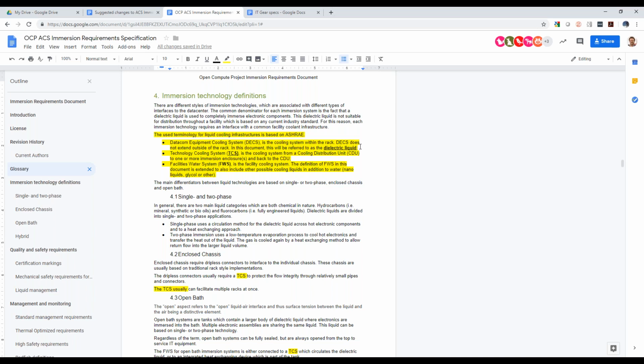There's no break between the CDU and the actual dielectric within the bath, just to understand your example. No, the dielectric liquid is pumped away from the bath to a cooling tower and then back into the bath. And that CDU is maintaining the mechanical circulation within those baths. That may be classified as a DEX. Right? Because I would classify it as a TCS, a technology cooling system, simply because it's a separate closed circuit. Yeah. You can compare it to cold plate.